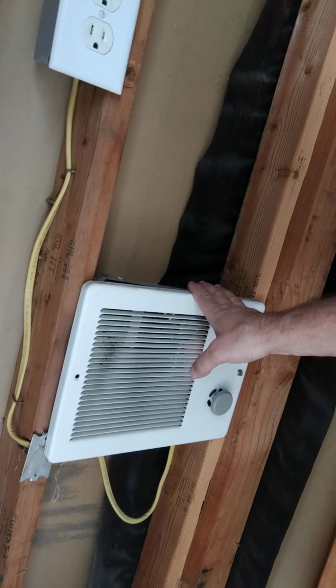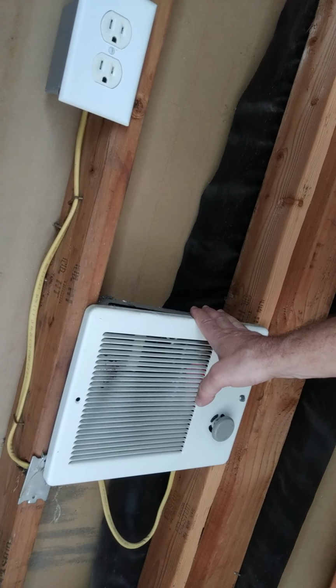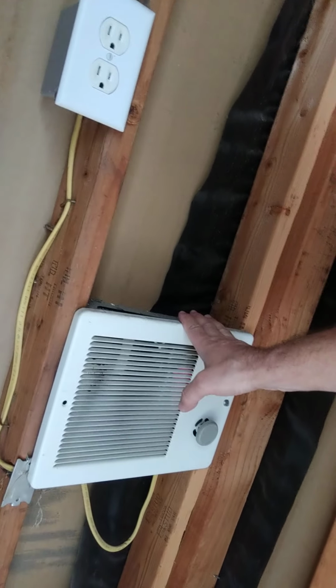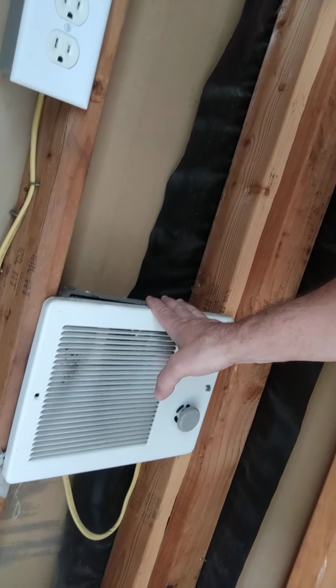Another real important thing in your riser room is your little space heater. If it ever gets so cold that you run the risk of freezing, you've got to make sure these things work. You don't need to make it 80 degrees in here, but you do need to keep it 55, 60 degrees when it's freezing cold outside. You don't want this stuff to freeze and burst and crack.